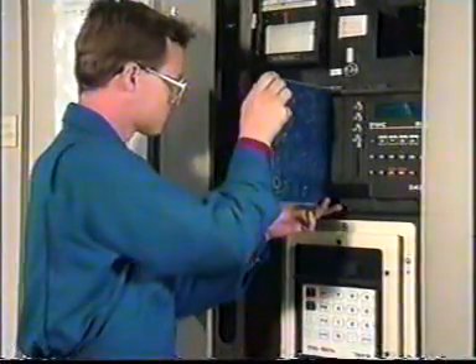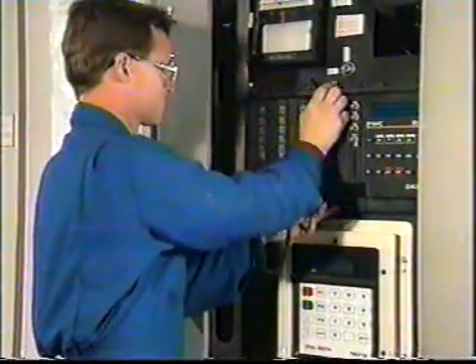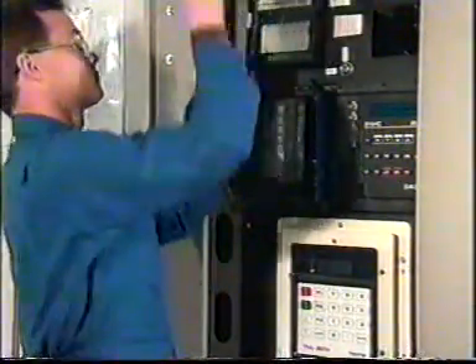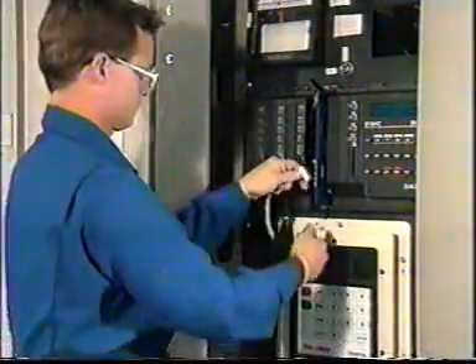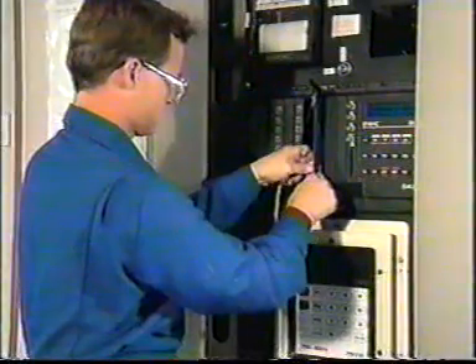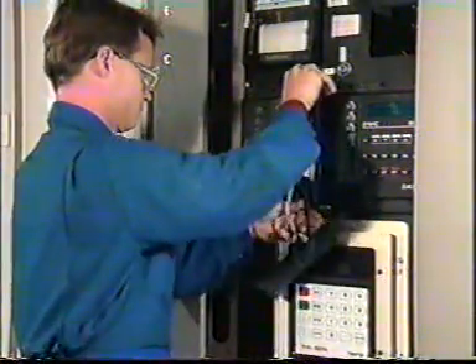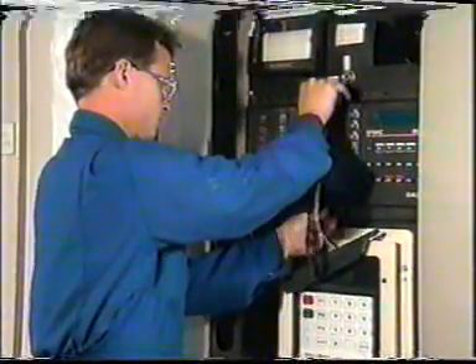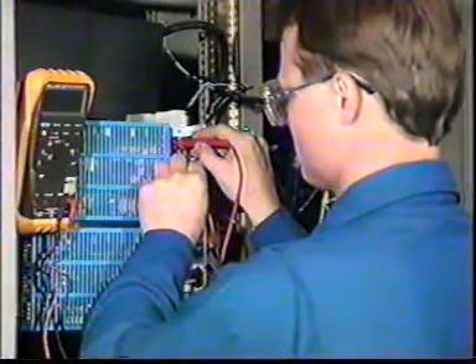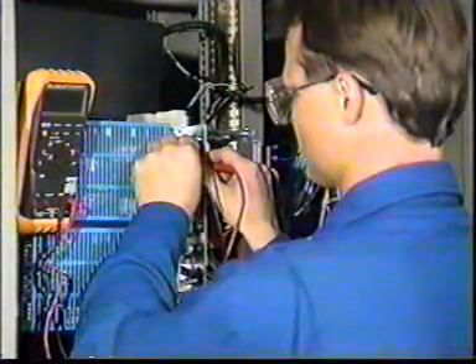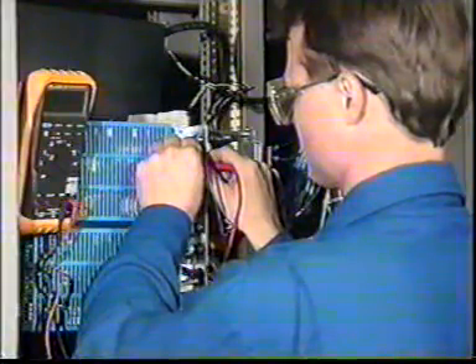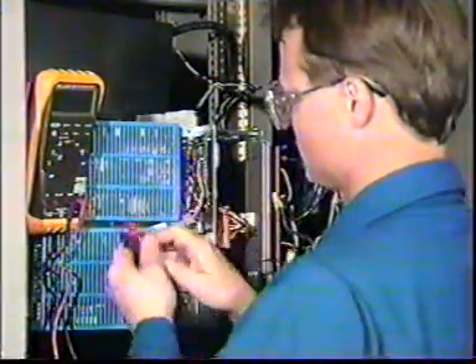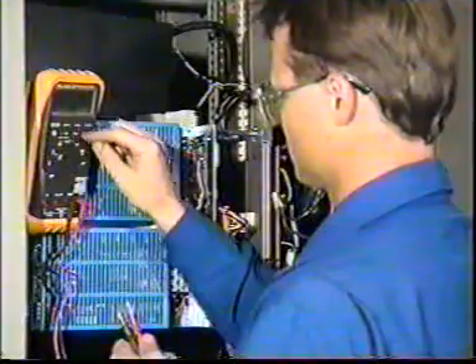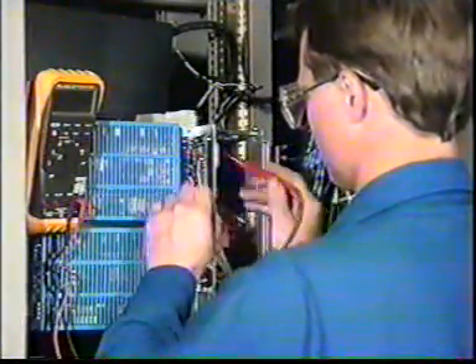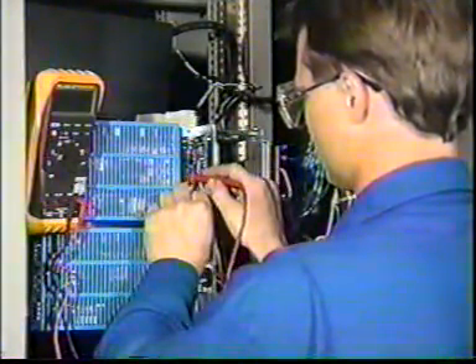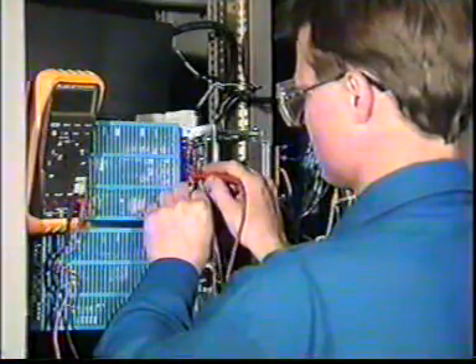Most installed monitoring systems use microprocessors to display, analyze, and store vibration data. If you need to replace a card or module, be sure to use static protection to keep from damaging replacement cards. Some systems require 2 power supplies for proper operation. Both the transducer and system monitor must have the same voltage levels. Before you replace a faulty power supply, check the voltage setting and adjust if required.